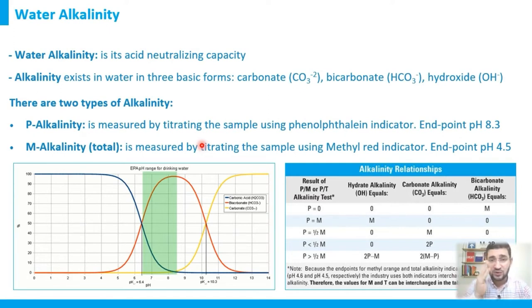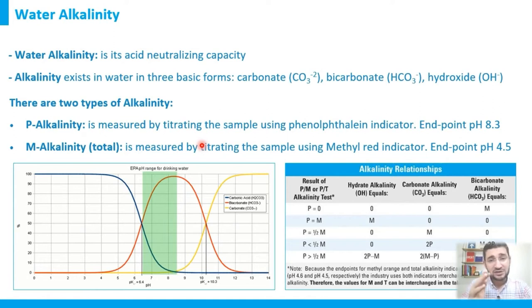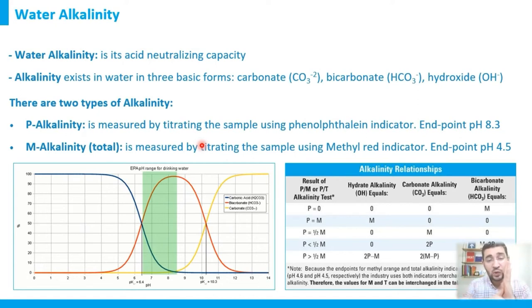P-alkalinity occurs when the water pH is above 8.3. If the pH is between 7 and 8, or below 7, there is almost zero P-alkalinity. As a rule of thumb: P-alkalinity only exists in water with a pH greater than 8.3. Below that, the result is essentially zero.